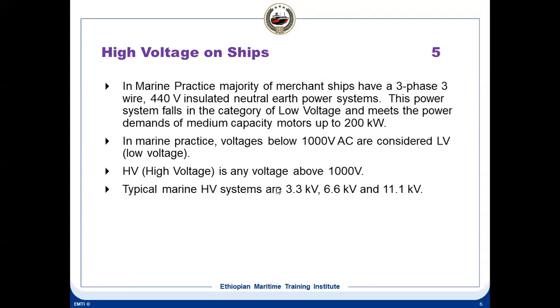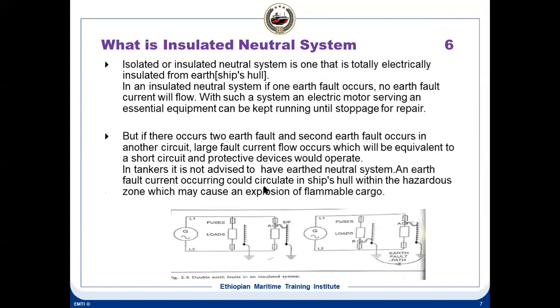Now here you must have seen it says 440 volt insulated neutral earth power systems. Okay, we'll just touch upon this. What is an insulated neutral system? Isolated or insulated neutral, it's almost the same. An insulated neutral system is one which is totally electrically insulated from the ship's hull. So in the insulated neutral system, if one earth fault occurs, no earth fault current will flow. With such a system, electric motors serving essential equipment can be kept running until a stoppage for repair. So this is the advantage of the insulated neutral system. Most 440 volt ships have the insulated neutral system.